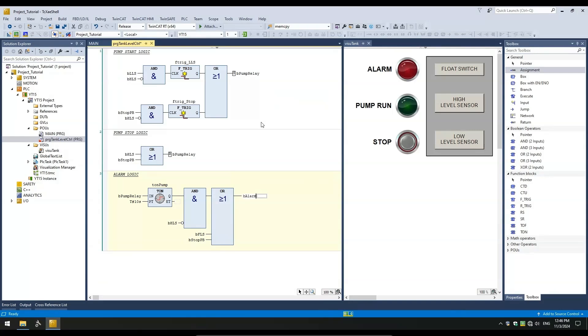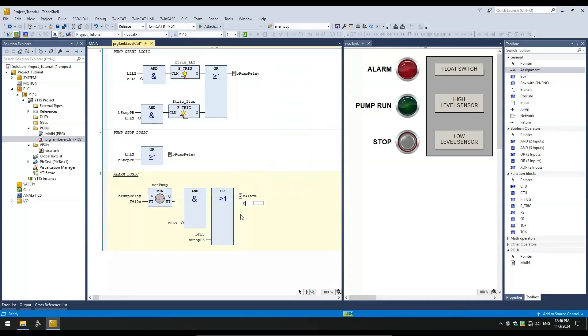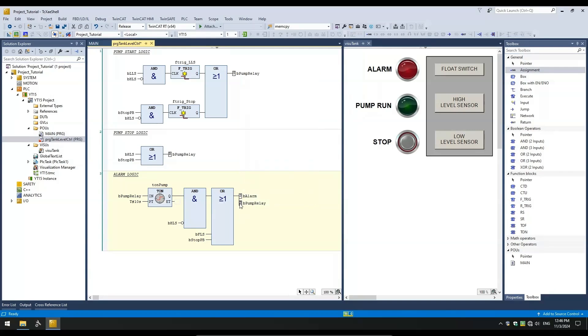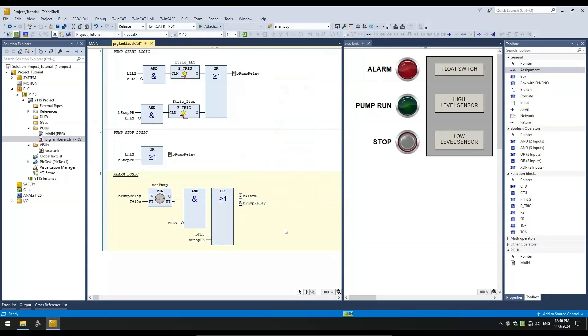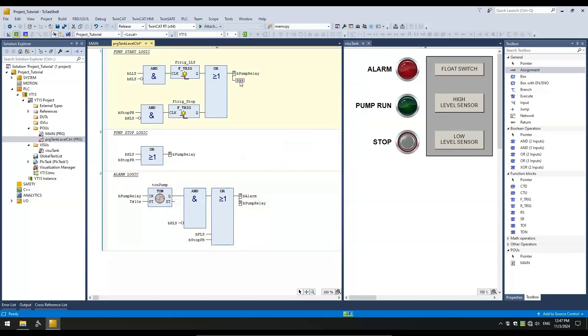For the output, we will set the alarm bit and reset the pump relay bit. Anytime an alarm occurs, the pump should stop. We can add another assignment variable to the same output by dragging the assignment element from the toolbox and dropping on the output pin. I will set this variable as a reset. We are almost done. One last thing remaining to do is resetting the alarm after it has been set. We can make it reset whenever the stop push button is pressed. We can add the alarm reset condition to the pump start logic.